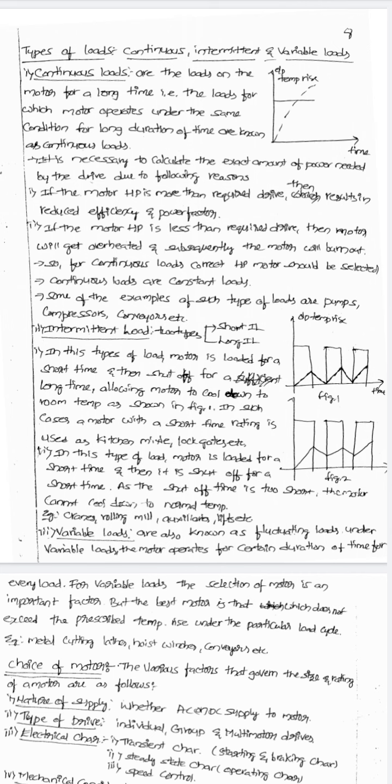Next, if the motor HP is less than the required drive, then the motor will get overheated and consequently the motor will be burnt. Keep the two cases in mind. First case, HP is more than the drive: the result is reduced efficiency and power factor. That is no problem. If it is less than the drive, the motor overheats and burns out.